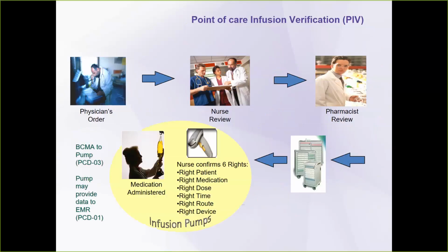Information is passed down between the infusion device and the programming system for confirmation that the device is programmed correctly for the order to be executed. The benefits of this would include better safety in the association of the device and a better record of that device association for record keeping as well.